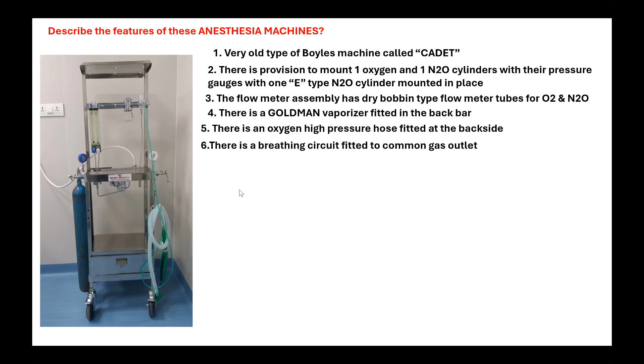And you can see a small projecting thing here. Can you identify what that is? Of course, if you see closely, it is an oxygen pressure hose coming and getting attached here. You can see it coming from the wall, and there is a breathing circuit coming out from the common gas outlet, which is hanging here, and just above the breathing circuit you have a valve called the APL valve.